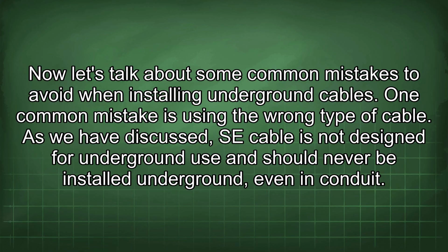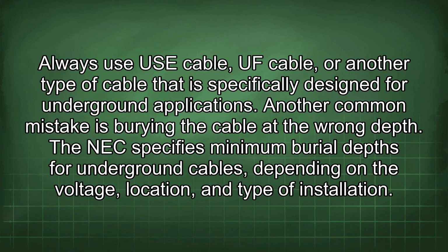One common mistake is using the wrong type of cable. As we have discussed, SE cable is not designed for underground use and should never be installed underground, even in conduit. Always use USE cable, UF cable, or another type of cable that is specifically designed for underground applications.